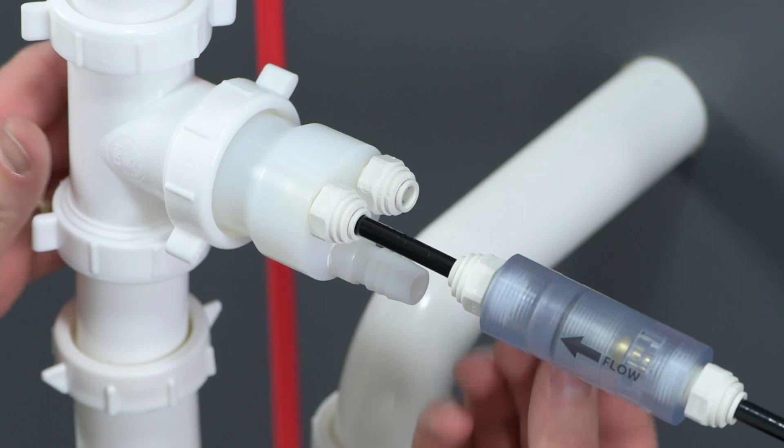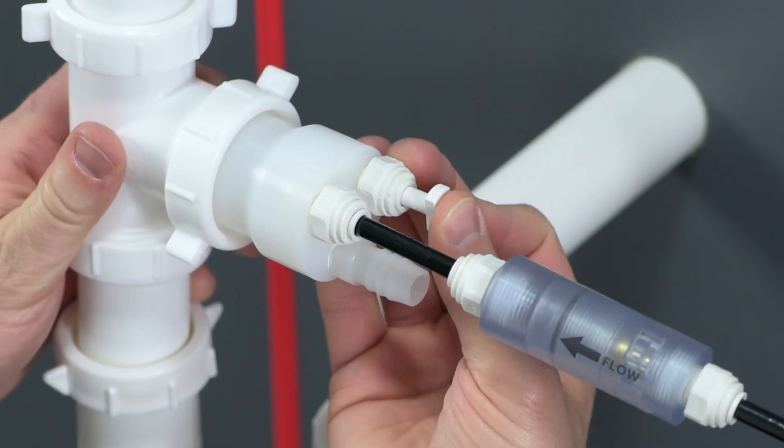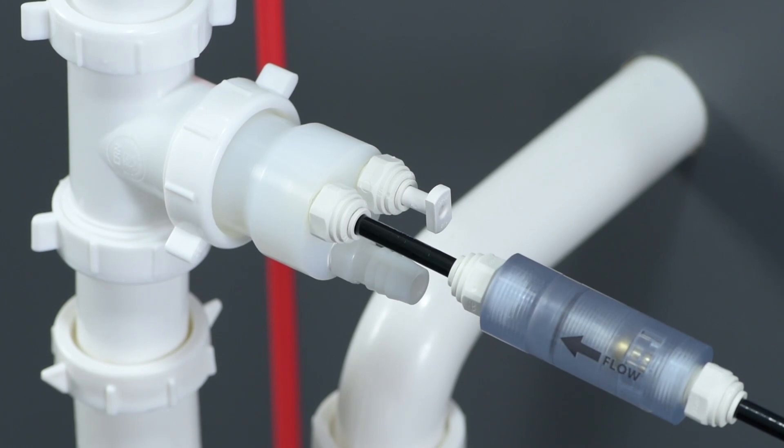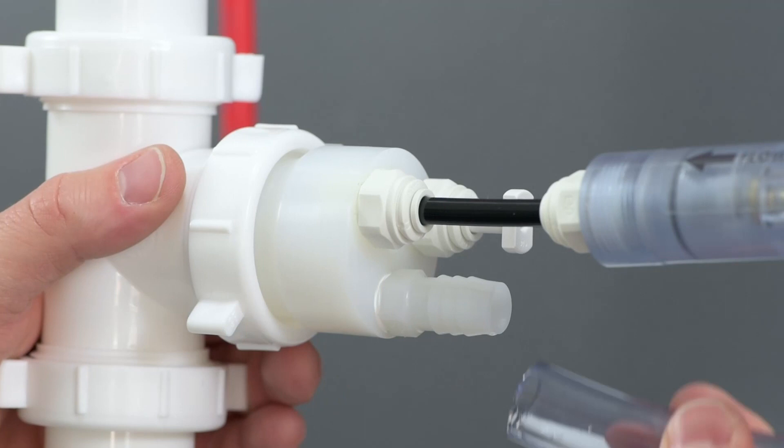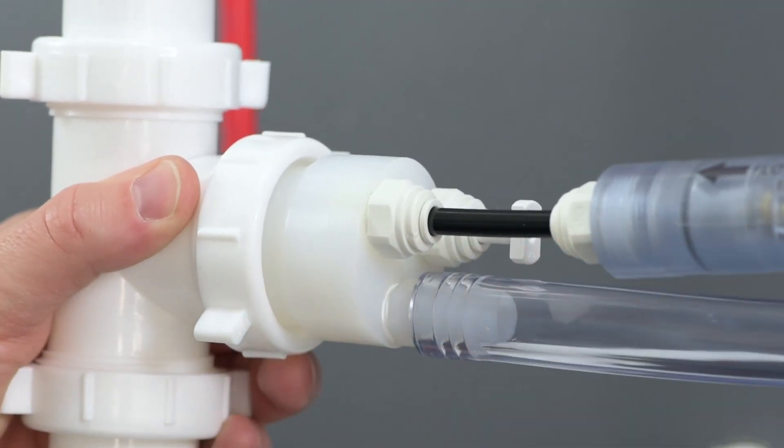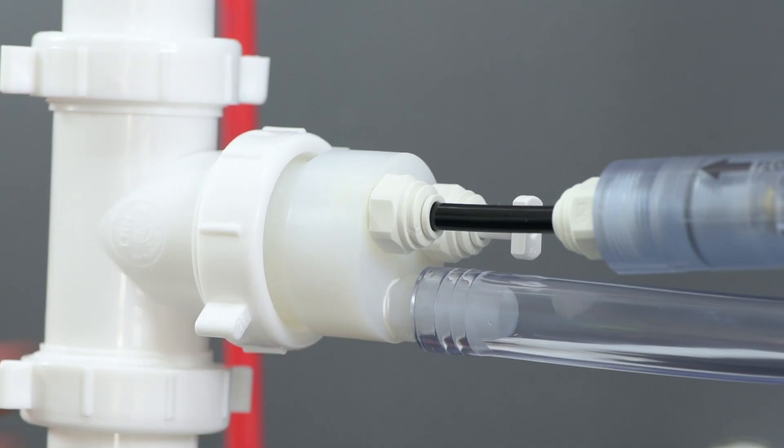If connecting only one autoclave to the VistaCool system, be sure the included plug is inserted into the second male adapter fitting on the drain adapter. Now connect one end of the half inch clear PVC tubing to the elbow hose barb on the tank and the other end to the straight half inch hose barb on the drain line adapter. Make sure the tubing is firmly engaged over the barbs. If in doubt, use appropriately sized hose clamps.